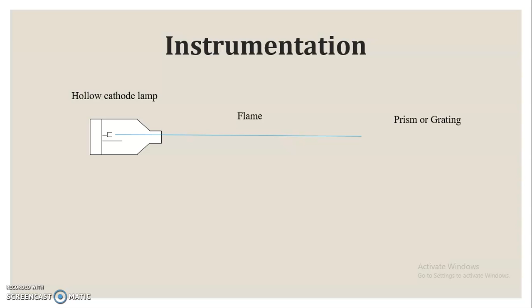Now here you can see this particular burner, which has a source from which the acetylene and air, meaning the oxidant as well as the fuel, is introduced at the bottom of the burner. Also, there is one entry point from which the sample solution will enter the burner. With the help of the nebulizer, like in flame emission spectroscopy, the solution will be aspirated into the burner, where the liquid will first be converted into liquid droplets. Further, the liquid droplets will be converted into the gaseous form, and once they are converted into the gaseous form, they will be introduced into the flame.